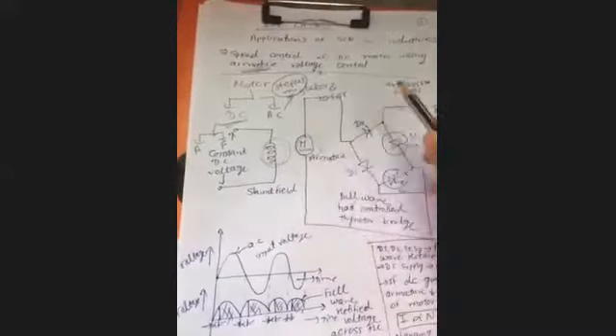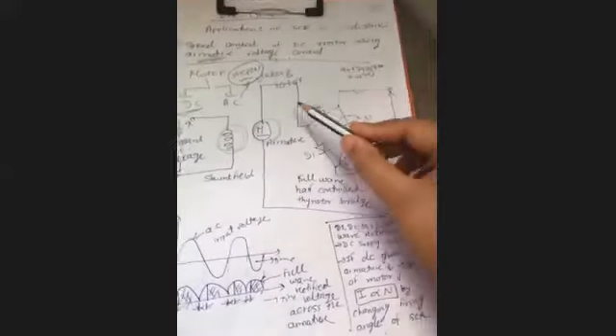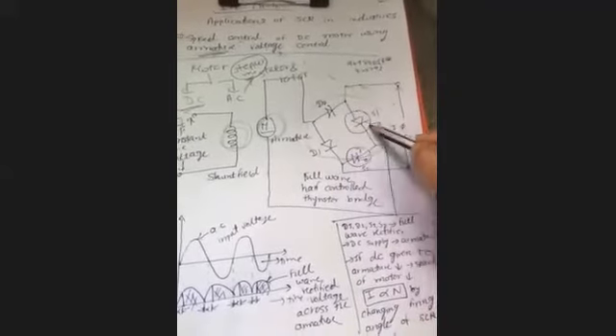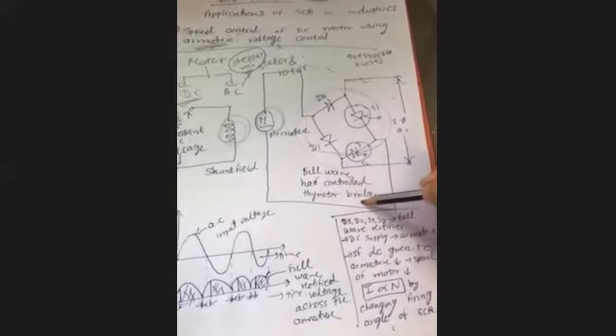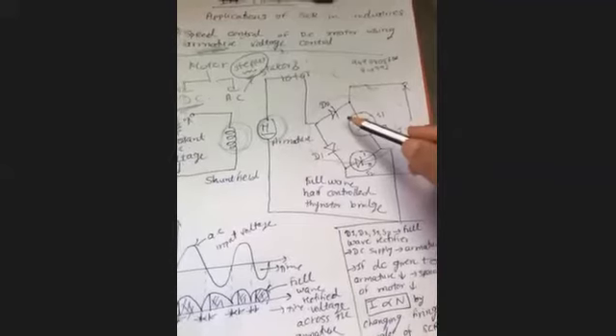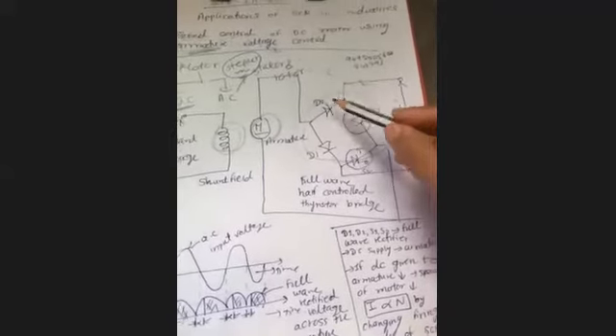This is the DC input voltage going into the armature. The circuit uses a full-wave half-controlled thyristor bridge converter, using 2 diodes and 2 SCRs. This half-controlled full-wave bridge provides the output to the armature.